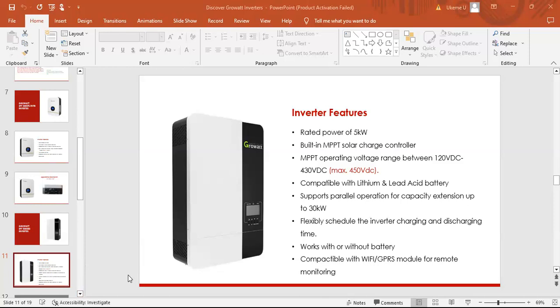Let's say, for example, you have a total load of 1 kilowatt and you want to run it without a battery system. Your PV array should be able to produce at least 1,500 watts or 2,000 watts for the system to work conveniently.